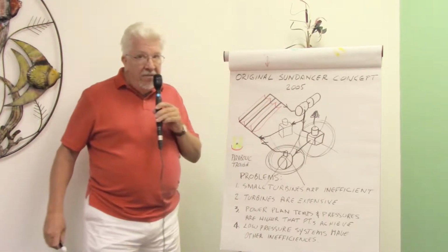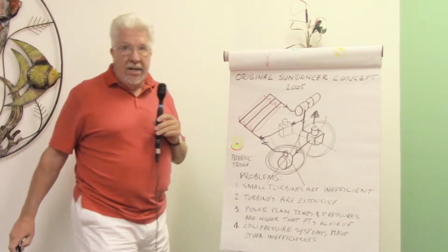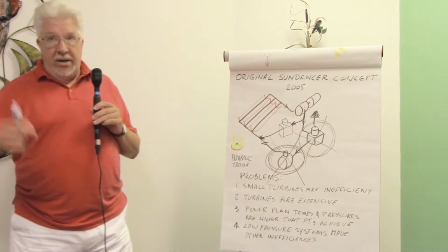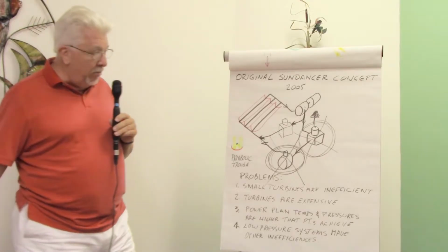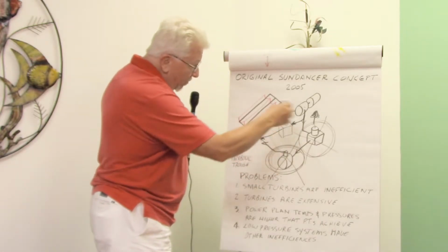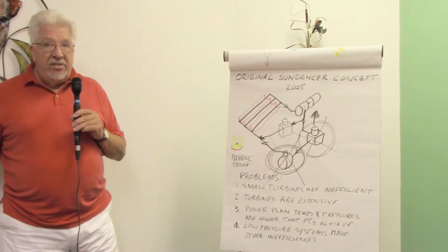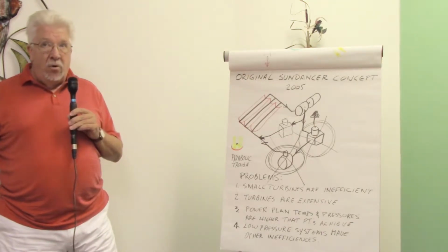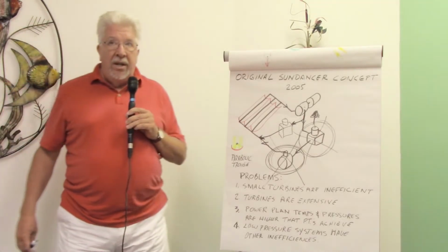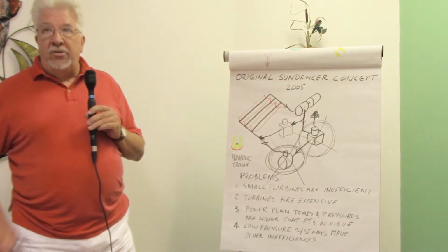This is a significant improvement in the efficiency of this system because the condenser losses go away. All right. As you're pumping stuff around, you're going to radiate some heat out into the environment through insulation. Insulation is not perfect, but those are the only losses in this system. Optimized reinjection as a method of dealing with the turbine exhaust is how we get this system to become significantly more efficient. It has a big, big, big effect. You're about to go through and see an array of pictures. These pictures all have legends on them, and you'll be able to see what it is we're talking about.